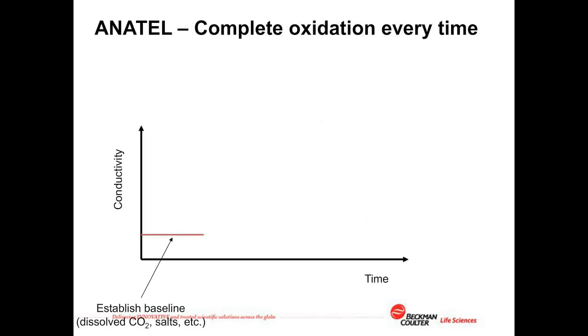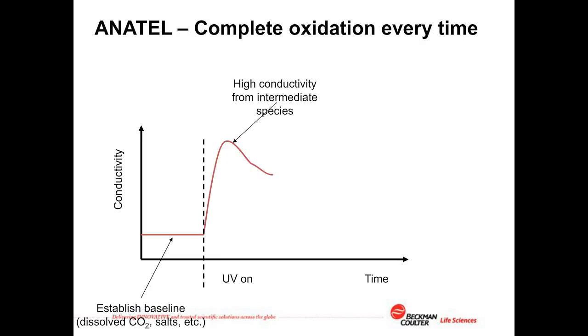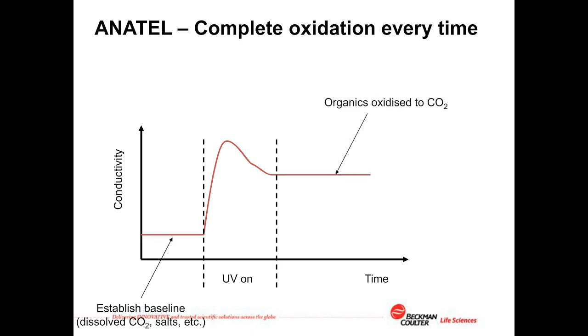The ANATEL PAT700 ensures complete oxidation every time. Initially, the conductivity of the water sample is measured to establish the quantity of baseline total inorganic carbon. Then the ultraviolet light is turned on. The PAT700 monitors the change in conductivity as the organic molecules are oxidized to carbon dioxide. When there are no further changes in the conductivity, the analyzer measures the new conductivity and compares it with the baseline total inorganic carbon conductivity. The difference in conductivity is directly proportional to the amount of organic material in the water sample.